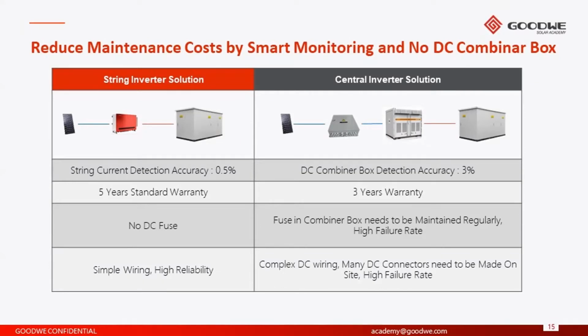By virtue of the fact that we have multiple MPPTs, we don't need to install string fusing, which also reduces the BOS costs and the maintenance costs. Typically in combiner boxes, we need to install the fusing, and it also needs to be maintained. With the string inverter solution, from the array to the inverter itself, it's a very simple DC connection. It's kind of like a peer-to-peer connection, where you have the PV arrays interfacing directly with the MPPTs without any intermediate component. Whereas in the centralized inverter solution, you have your PV array connected to a string, to a DC combiner box, which is then connected to the inverter and then connected to the on-site transformer.